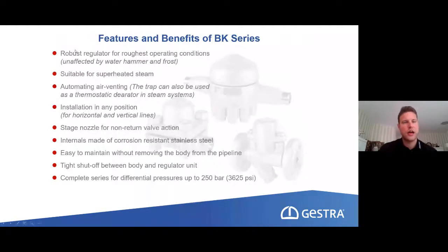So it's, I would say, the most robust regulator for tough conditions. It also works on superheated steam, which is typical for BK, so usually also in power plants. It has automatic air venting because it's a thermostatic steam trap, so it detects colder temperatures. So also when air is in the system, it will detect it and discharge as long as we have not reached steam temperature.